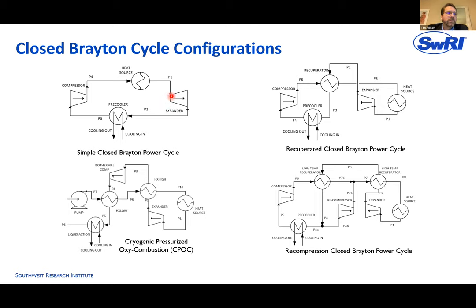With supercritical CO2, you can improve the efficiency a lot by going through recuperation. This is sometimes done on gas turbines as well, but with a recuperated cycle, you cool, you go through a compressor, and then you actually pick up heat from the turbine exhaust before you go to your primary heat source. That's done through a heat exchanger called a recuperator.